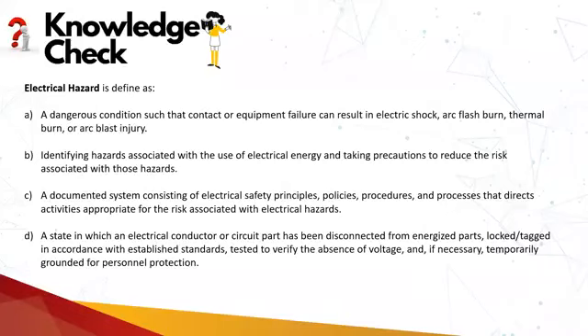Yeah, the right option is a dangerous condition such that the contact or equipment failure can result in electric shock, arc flash burn, thermal burn, or blast injury. So Annex K of this standard talks about the electrical hazards, and this standard only talks about the hazards related to the use of electricity. So in this standard, you won't be finding hazards related to trip hazards or falls from height while working on overhead poles and towers. No, those are not covered in this standard.